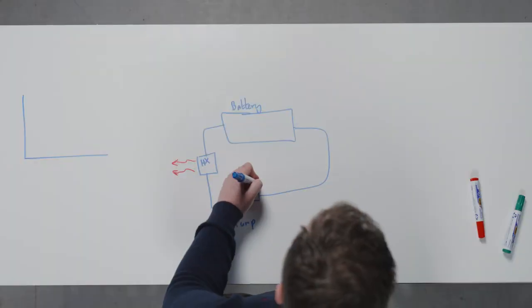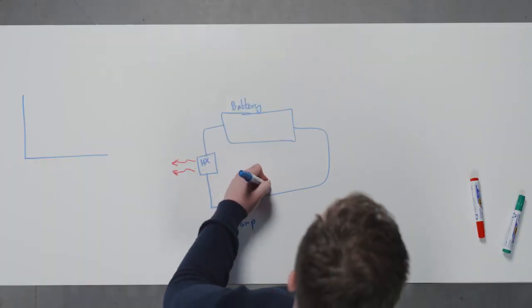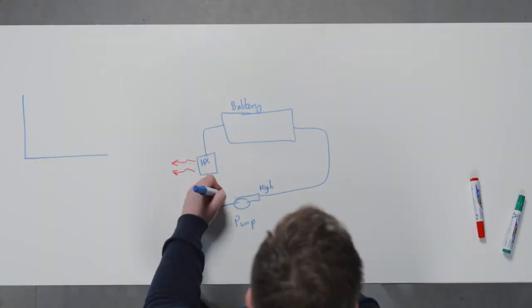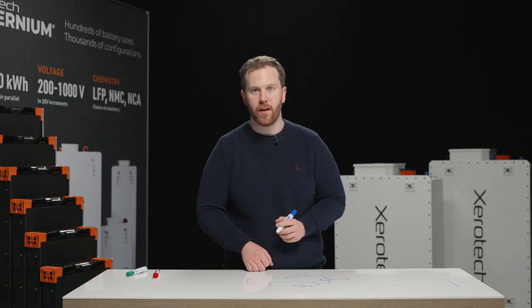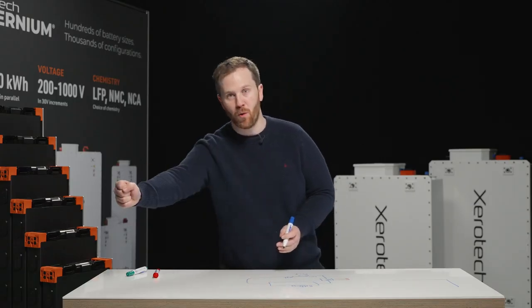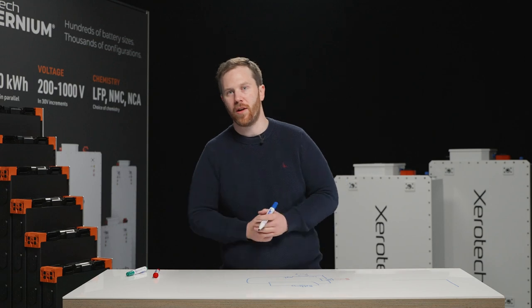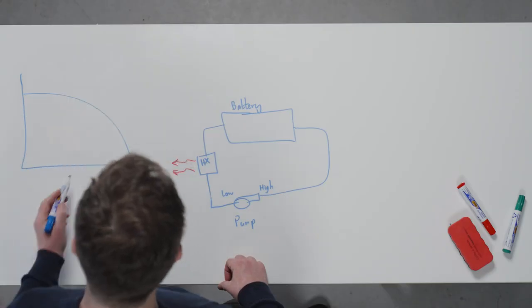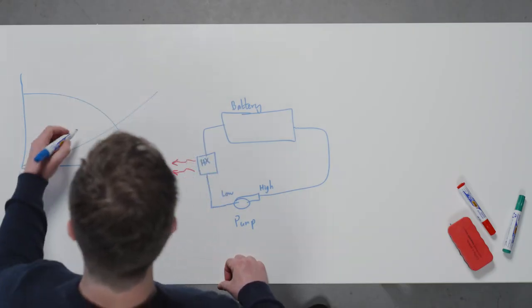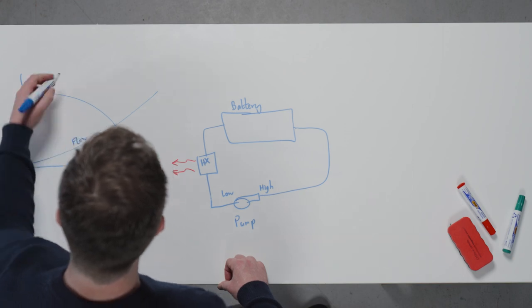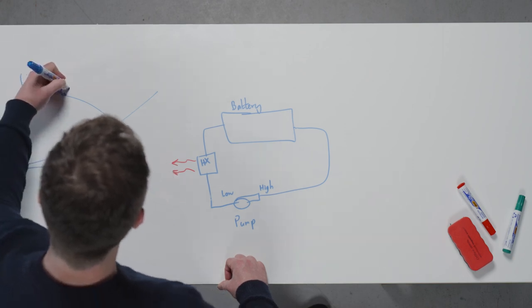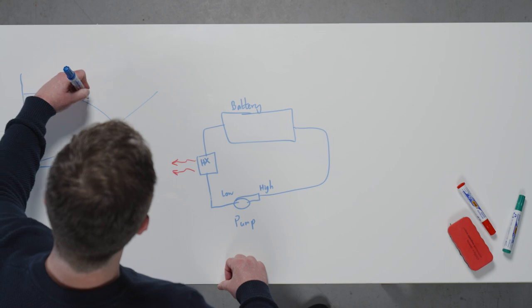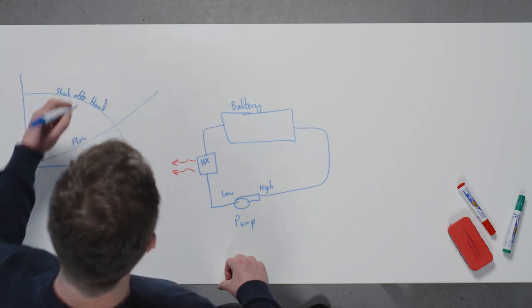So all pumps have a very basic function. They move water or a liquid from one point to another. And the way they achieve that is they develop high pressure on one side of the pump and low pressure on the other side. Basically, they push water out one side of the pump and they suck water in the other side. So we're going to look at the characteristic curve of any pump, or a typical centrifugal pump that's in a battery system. We've got the shut-off head pressure here and then the flow rate here.